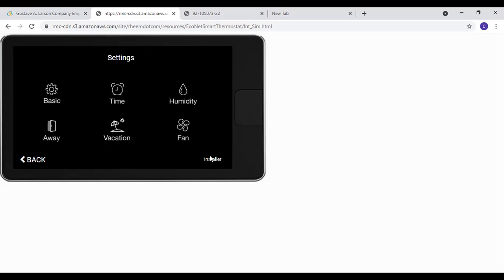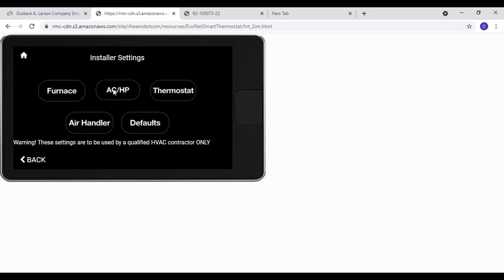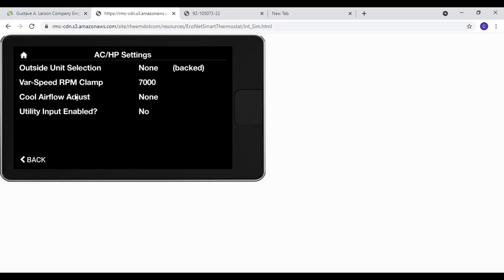Now, if you had to adjust your airflow a little bit, say you were just on the borderline, you could go in here to this installer. You could go into the AC heat pump. Right here, you'll see what they call cool airflow adjust. Out of the box, it's going to be set at the optimal factory CFM. If you need to go down some, you can highlight the none and then go down to the lowest section, or if you need to increase it a little bit for whatever reason, you can highlight that and go up.